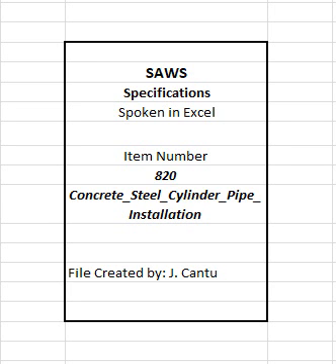26. Perform minimum of one set of weld test specimens in accordance with ANSI/AWS A3.0 on each size, grade, and wall thickness at minimum of every 3,000 feet of pipe manufactured. A. Perform no less than one test per project by each welding machine and each operator. 27. Make available copy of physical and chemical testing reports and provide reports at request of SAWS engineer or inspector.